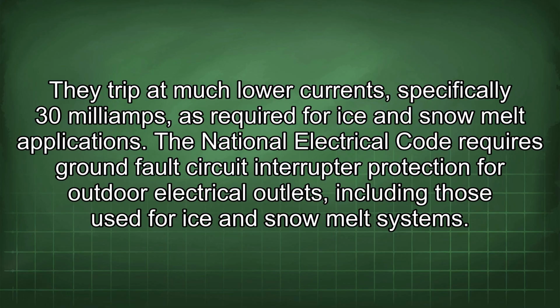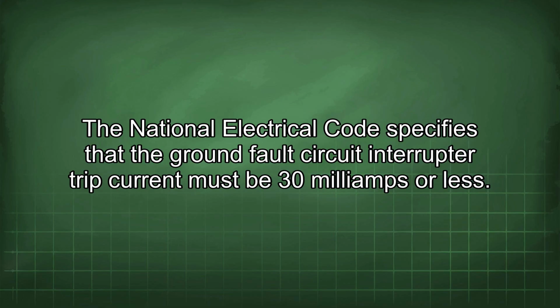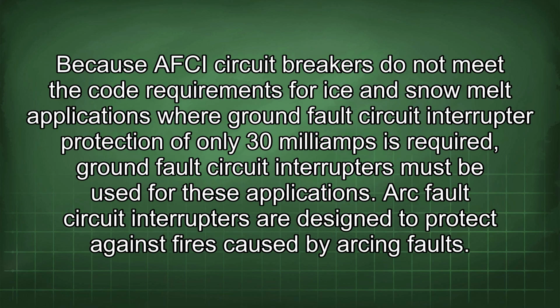The National Electrical Code requires ground fault circuit interrupter protection for outdoor electrical outlets, including those used for ice and snow melt systems. The National Electrical Code specifies that the ground fault circuit interrupter trip current must be 30 mA or less. Because AFCI circuit breakers do not meet the code requirements for ice and snow melt applications where ground fault circuit interrupter protection of only 30 mA is required, ground fault circuit interrupters must be used for these applications.